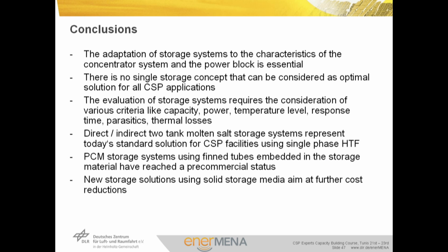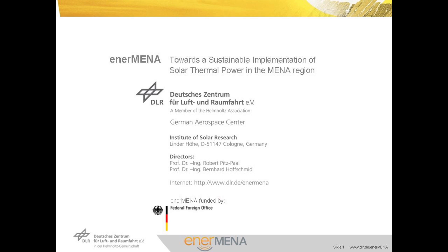In conclusion, adaptation of storage systems to the characteristics of the concentrator system and power block is essential, and there is no single storage concept optimal for all CSP applications. Evaluation requires consideration of various criteria including capacity, power, temperature level, response time, parasitics, and thermal losses. Direct and indirect two-tank molten salt storage systems represent today's standard solution for CSP facilities using single-phase HTF. PCM storage systems using finned tubes embedded in storage material have reached a pre-commercial status. New storage solutions using solid storage media aim at further cost reductions. This work was supported by the enerMENA project through the German Federal Foreign Office.